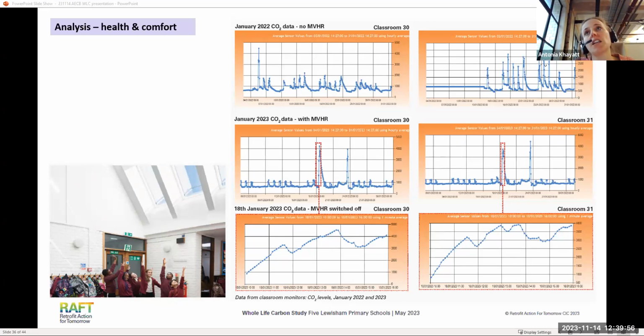What we can see in the top graphs is that for long periods of time, carbon dioxide levels within those classrooms are well over 1,000 or 1,500 parts per million for large parts of the day. Whereas once the MVHR has gone in, we're generally under 1,000 parts per million. We think that around 1,000 parts per million or less is okay, and 1,500 or more is really not good.